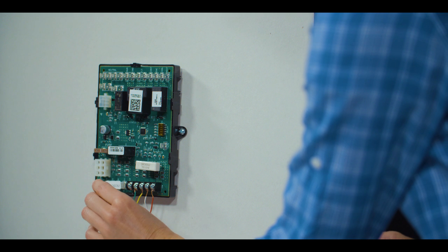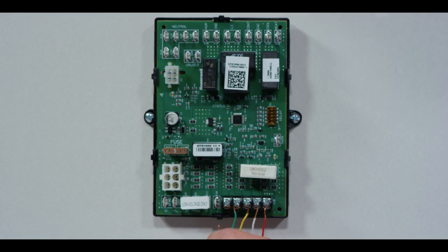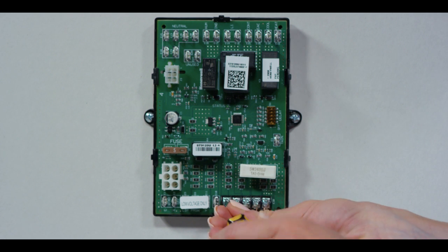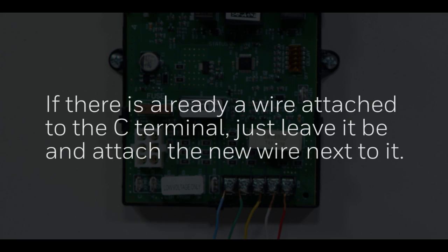Trace the extra unused wire from the thermostat to the furnace board. Make sure it's connected to the C terminal. If there's already a wire attached to the C terminal, just leave it be and attach the new wire next to it.